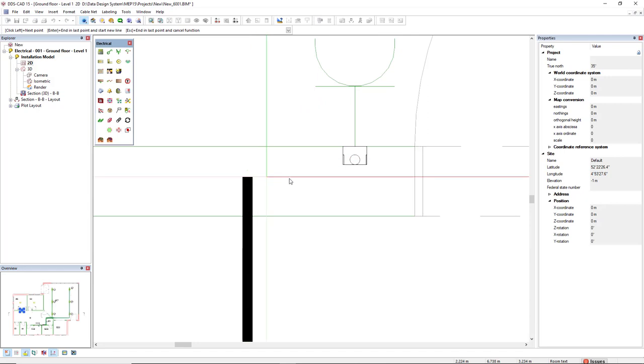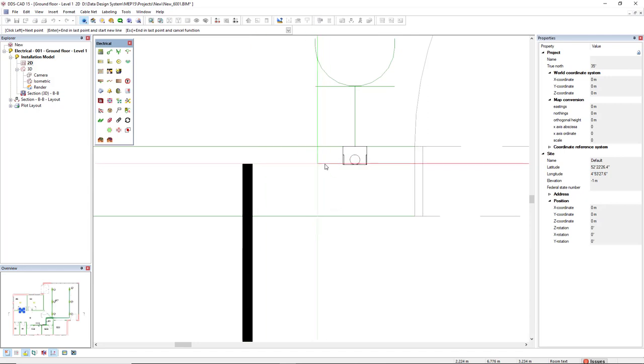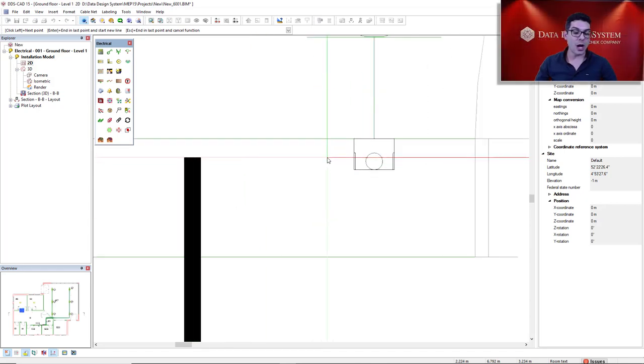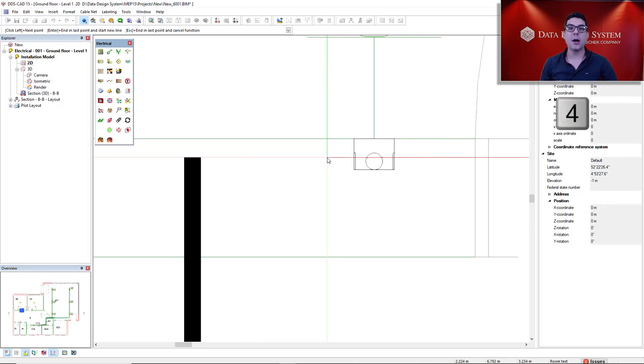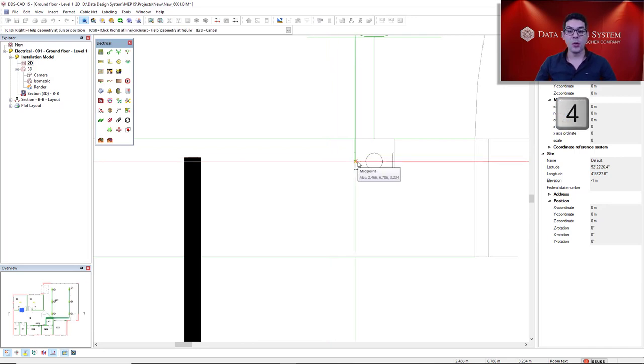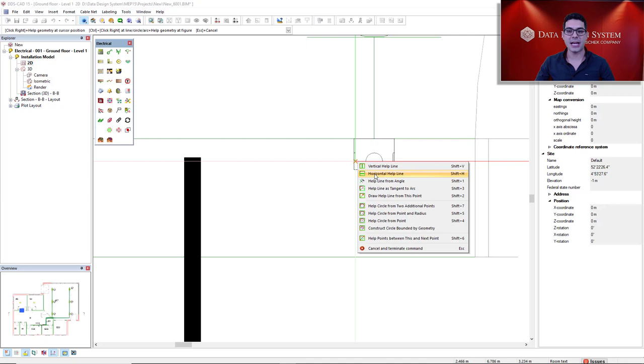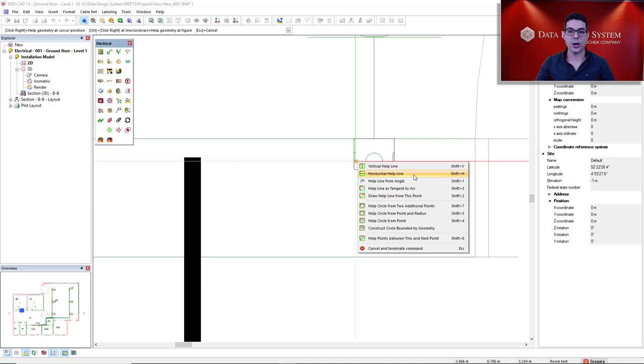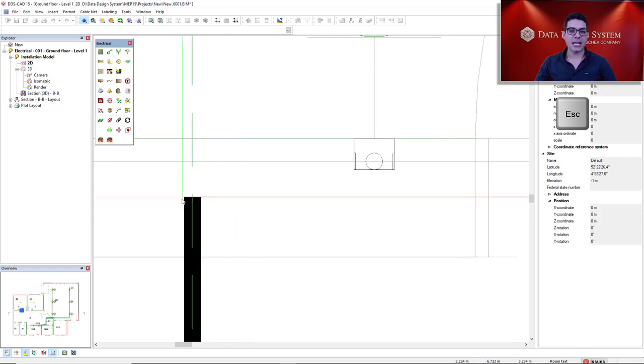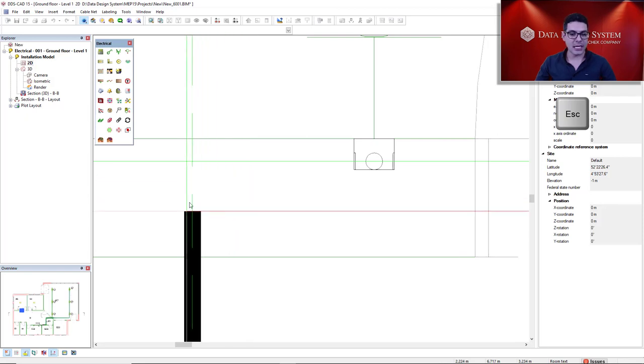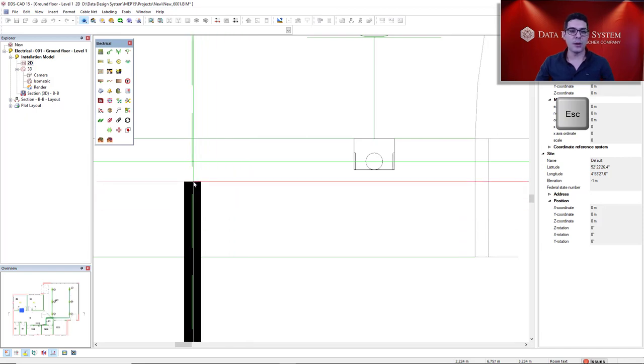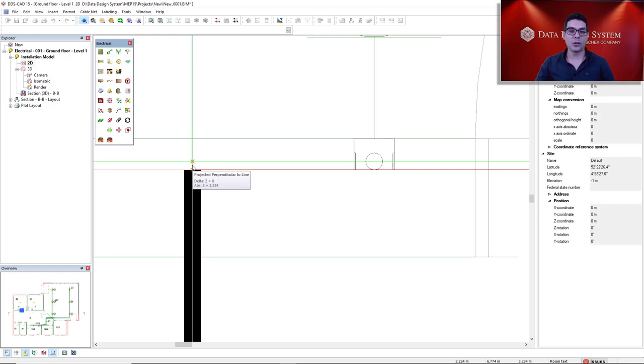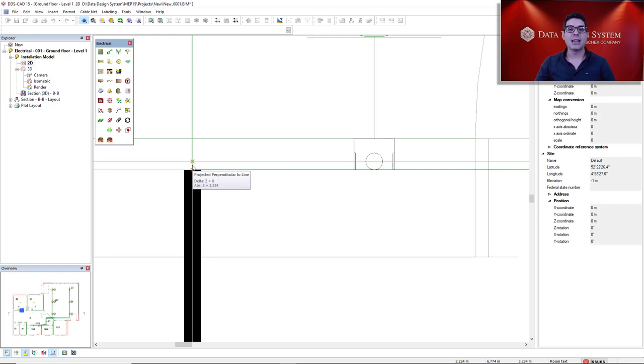I have to find the alignment with this junction box connection. So I will make use of the hotkey number 4, and then move my cursor to the snap in the connection of this junction box. Right mouse click and I will make use of this horizontal helpline. Now I press the Esc key, and I can keep working with my conduit. By moving close to this helpline you will see a projected perpendicular to line. Left click.